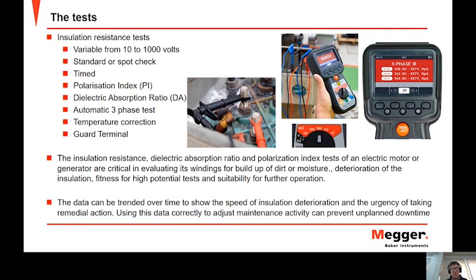So let's look at the tests one by one, starting with insulation resistance. The IR tests have preset voltage levels of 50, 250, 500 and 1 kV. And there's also the ability to set any voltage between 10 and 1 kV in 10 volt increments. And that's done through the settings screen.